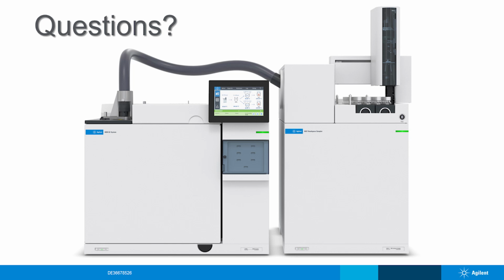Most commonly we see 20 milliliter headspace vials, but we have seen microliter amounts where you're essentially vaporizing the entire sample, all the way up to 10 to 12 milliliters of water-based samples. So it really depends on the application.